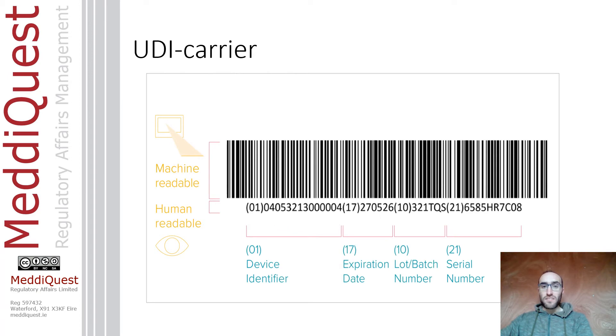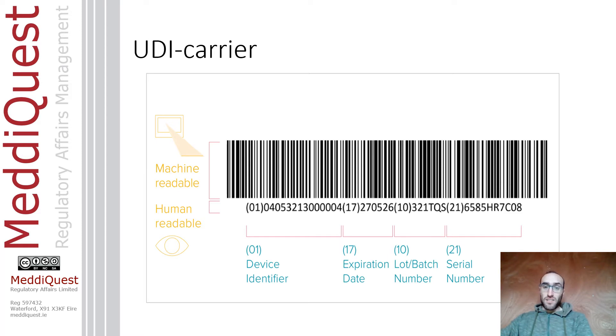The UDI carrier is the format in which you can see the UDI. There are two parts: the Automatic Identification and Data Capture (AIDC), a technology used to automatically capture data including barcodes, smart cards, biometrics, and radio frequency identification; and the Human Readable Interpretation (HRI), which is a legible interpretation of the data characters encoded in the UDI carrier, important when no automatic system is available. The UDI-DI is the number after the indicator '01' in brackets, which is the placeholder for the UDI-DI.